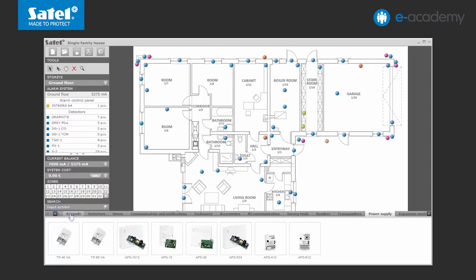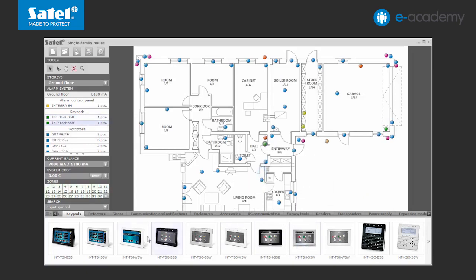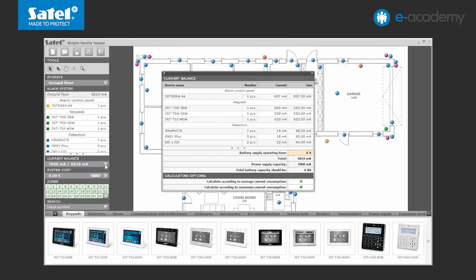Now let's add keypads to the system. Select the touchscreen keypads: INT-TSG, INT-TSH and INT-TSI. Having put the selected devices onto the drawing, you can check their current balance. In the side menu under Current Balance Selection, you will find detailed information on the current consumption of the entire system and its individual components. At the same place, you can also define how much time your system should run on battery power. The configurator will automatically calculate what battery capacity is needed so that the system can operate for the time specified.